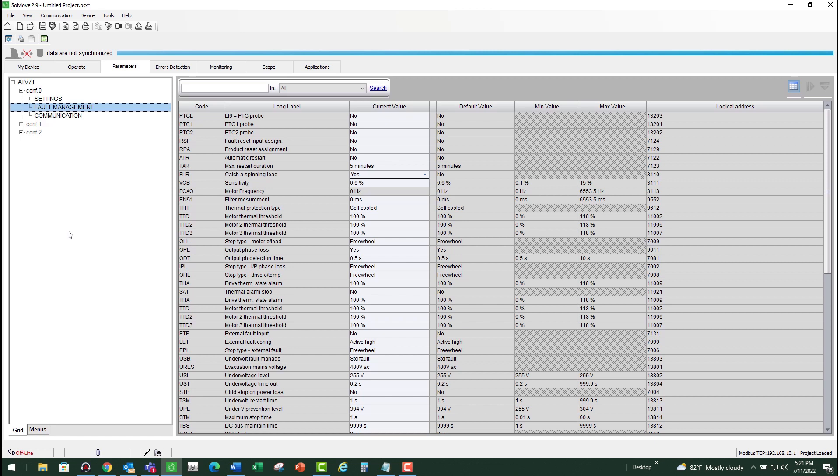The OBF fault can also occur because of power issues or power disturbances, so you need to check, for example, transformer, line load reactors, etc. You can also measure line voltage on L1, L2, L3 terminals of the VFD and measure phase-to-phase voltages. Make sure the voltage is within tolerance.